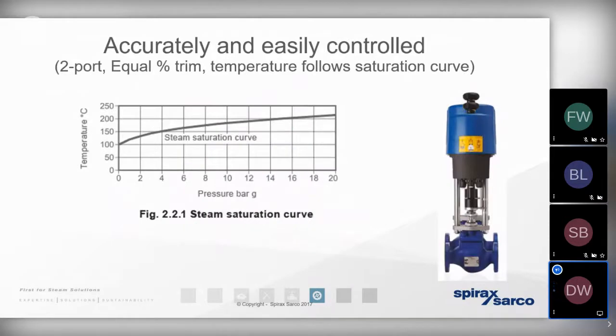And I just want to come back to that direct pressure temperature relationship that we've spoken about. The steam saturation curve that we can see above, as we've gone through in previous presentations, demonstrates that if we know the pressure of the steam, we know its temperature. For example, if we're distributing steam in the pipework at 10 bar gauge, the steam saturation curve tells us that the temperature of the steam is 184 degrees.